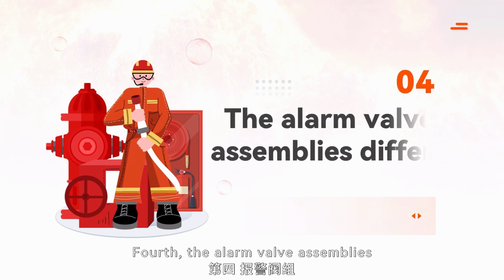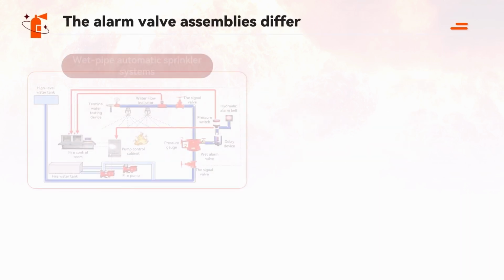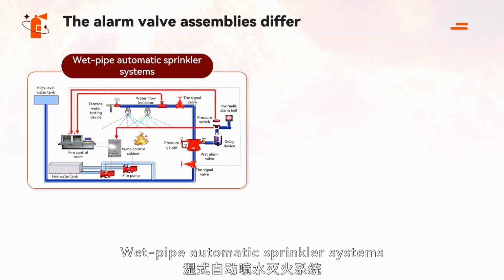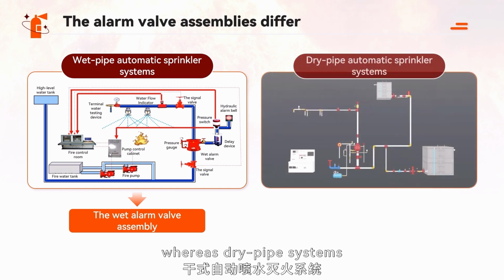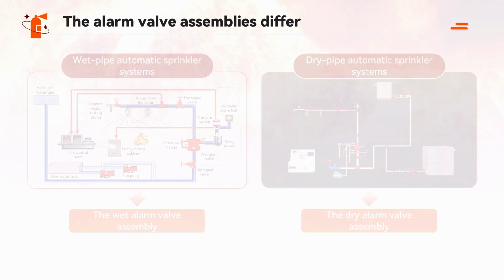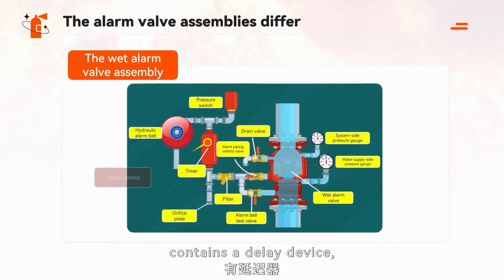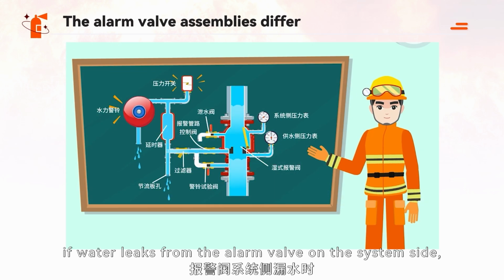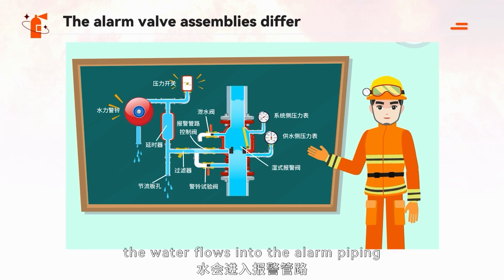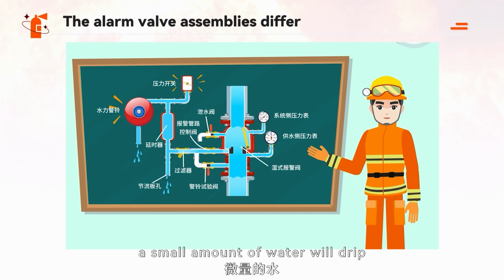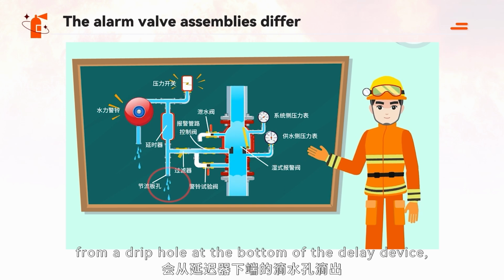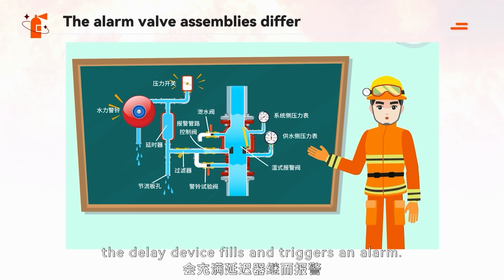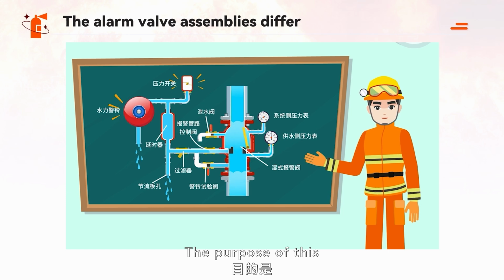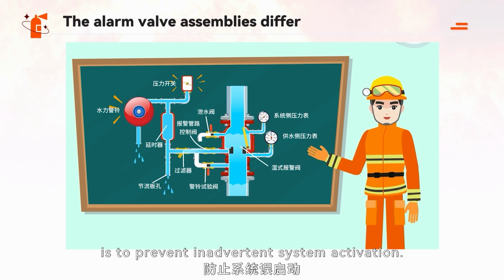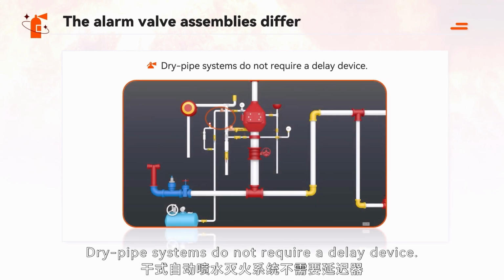Fourth, the alarm valve assemblies differ between the two systems. Wet pipe automatic sprinkler systems use a wet alarm valve assembly, whereas dry pipe systems use a dry alarm valve assembly. Specifically, the wet alarm valve assembly contains a delay device, which the dry system lacks. In a wet pipe system, if water leaks from the alarm valve on the system side, the water flows into the alarm piping and then into the delay device. A small amount of water will drip from a drip hole at the bottom of the delay device, and if a large amount flows in, the delay device fills and triggers an alarm. The purpose of this is to prevent inadvertent system activation. Dry pipe systems do not require a delay device.